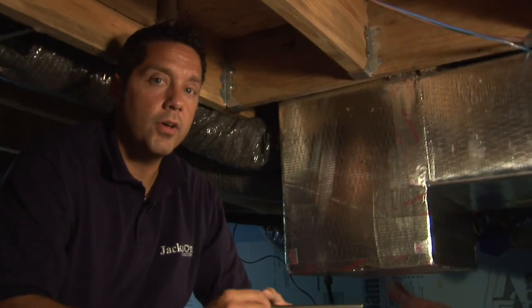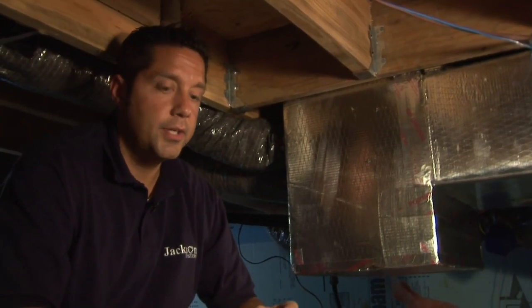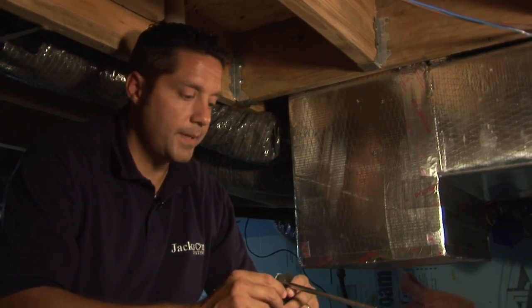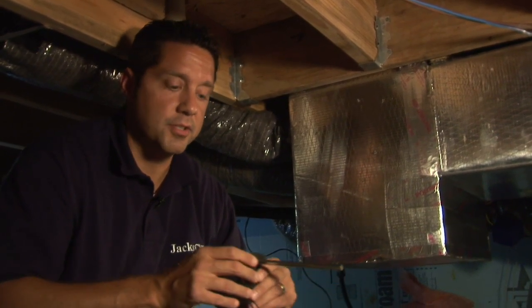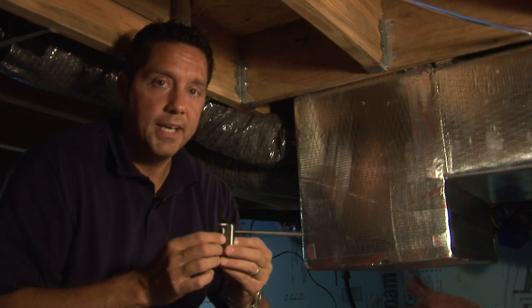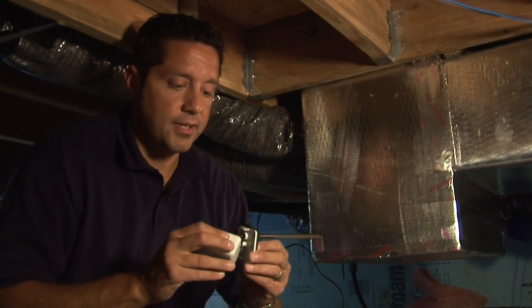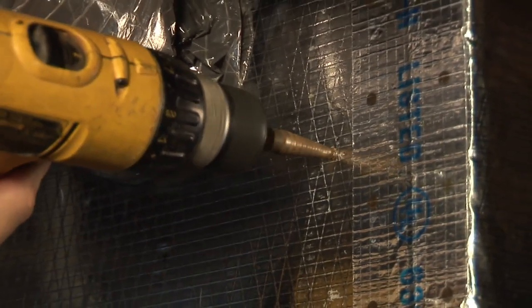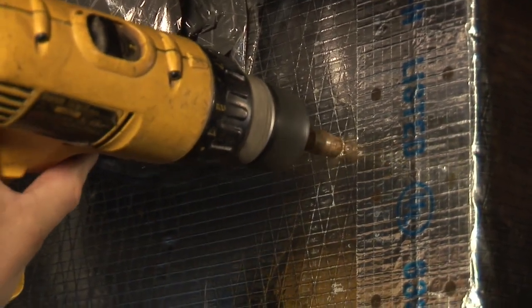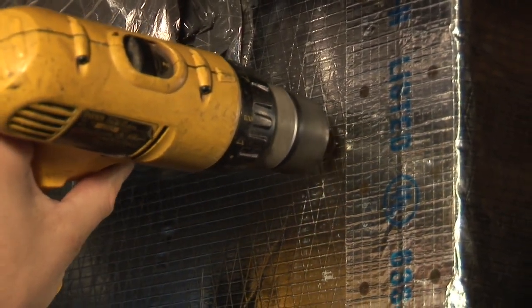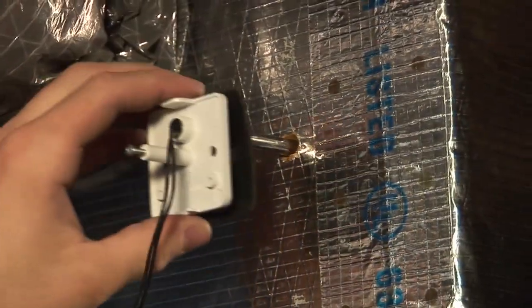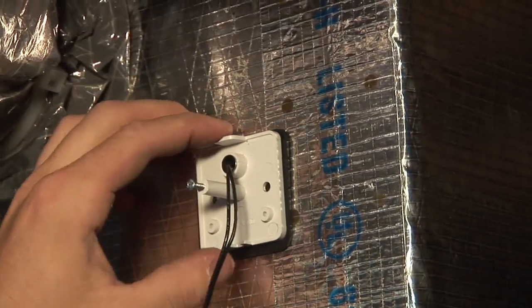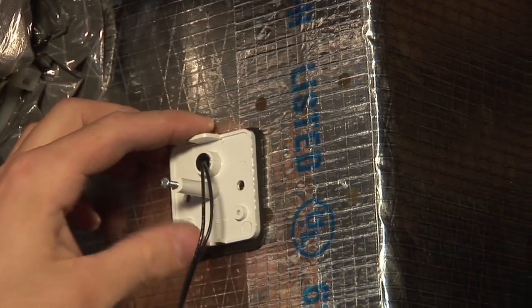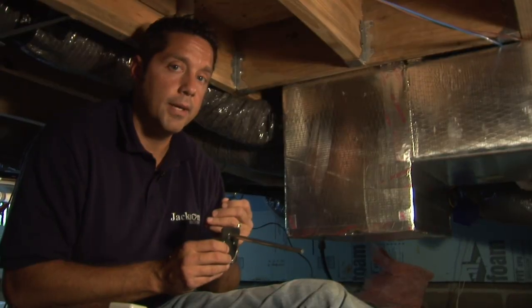Now that we've installed all the zone dampers, we are going to finish up down here in the crawl space by installing the discharge air sensor, which is what I hold in my hand. The discharge air sensor acts as the high and low limit for the zone control system. We're actually just going to drill a small hole into the ductwork and insert the discharge air sensor, and then it just requires 2 wires to this device back up to the panel, and we'll be ready to go.